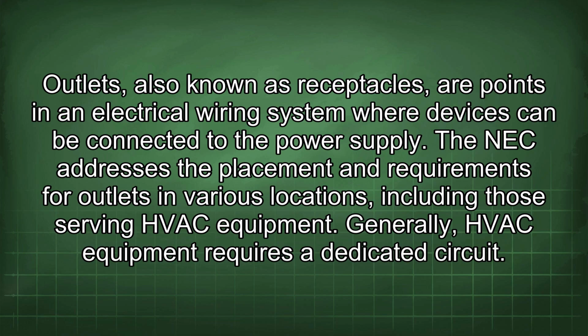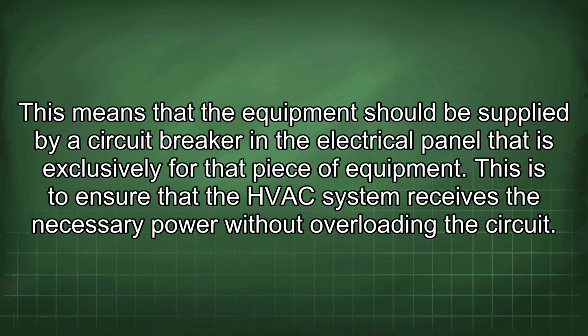Outlets, also known as receptacles, are points in an electrical wiring system where devices can be connected to the power supply. The NEC addresses the placement and requirements for outlets in various locations, including those serving HVAC equipment. Generally, HVAC equipment requires a dedicated circuit. This means that the equipment should be supplied by a circuit breaker in the electrical panel that is exclusively for that piece of equipment. This is to ensure that the HVAC system receives the necessary power without overloading the circuit.